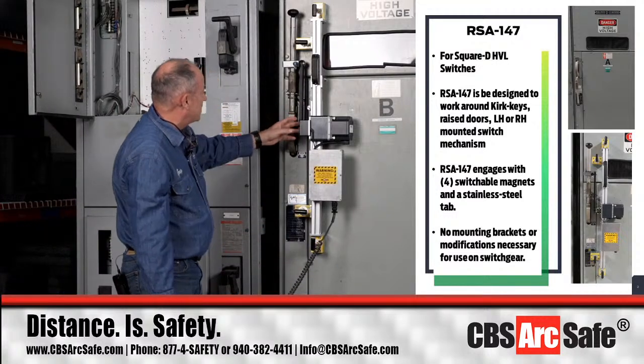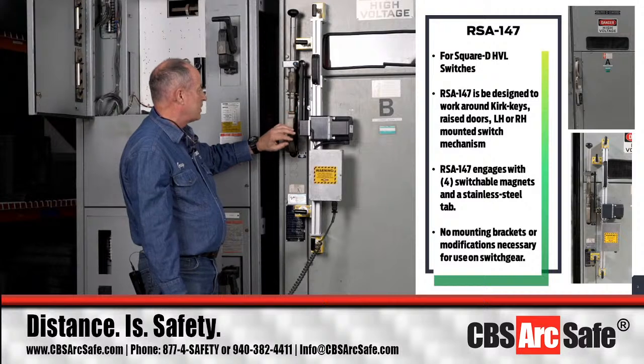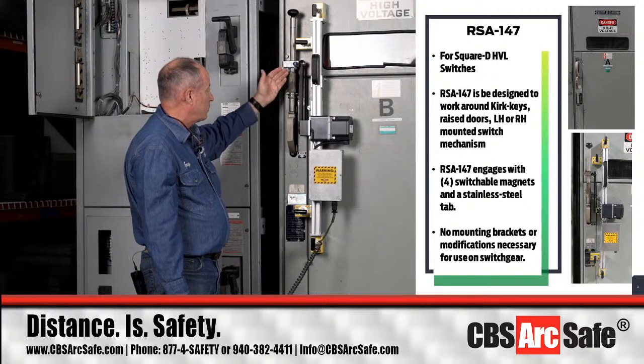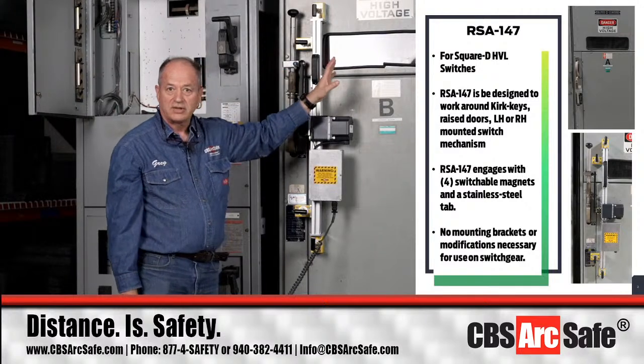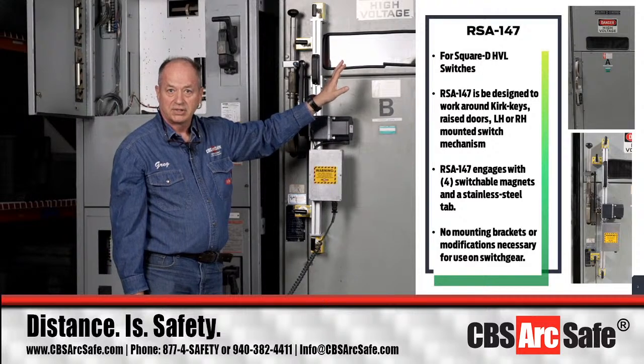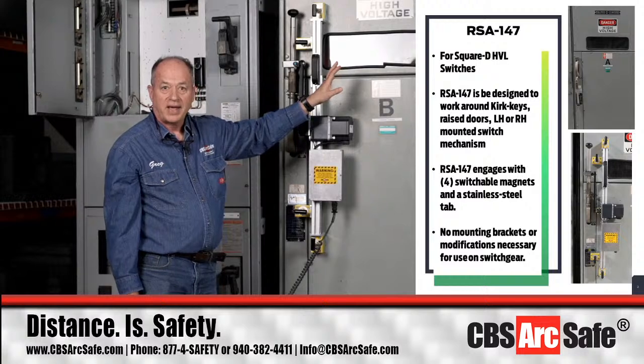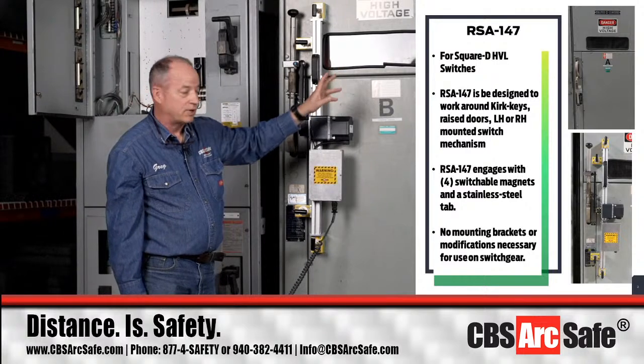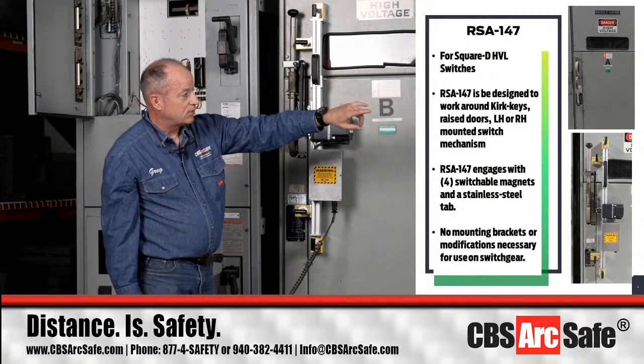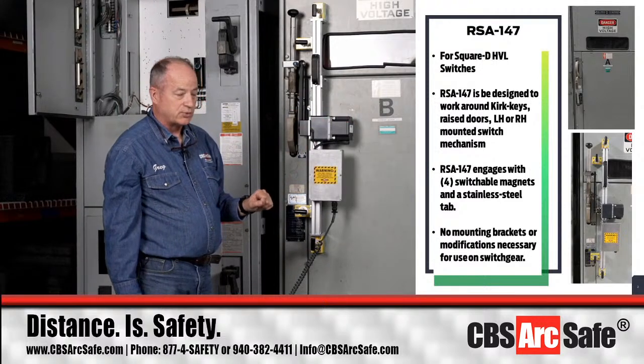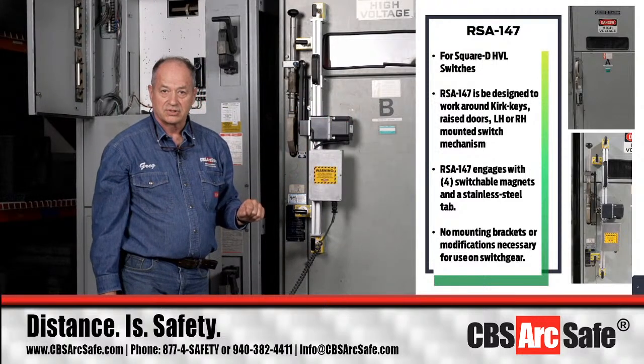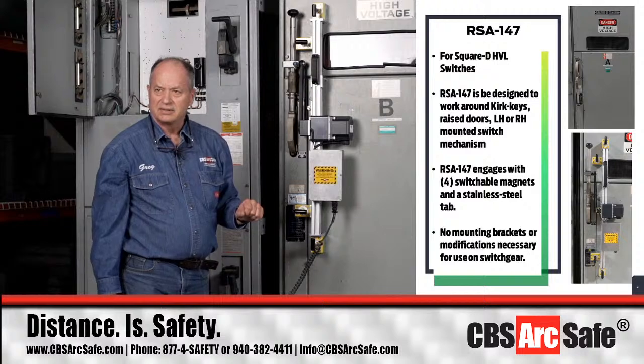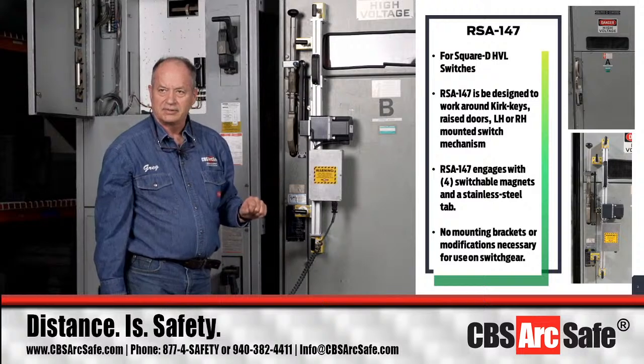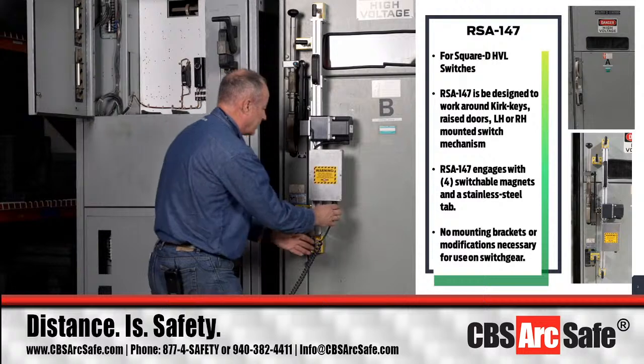This actually has a set of micro switches for the travel limit, set up so that we complete the operation and don't try to go past the physical limits of the switch, because of the way the knife blade switch operation is. We use that also on the remote switch actuator you'll see for the Westinghouse LSI or WLI switch that we're going to do here in a couple minutes.